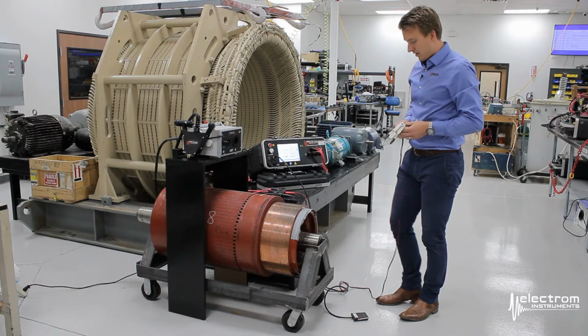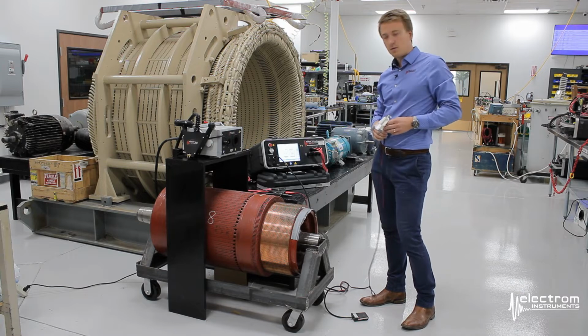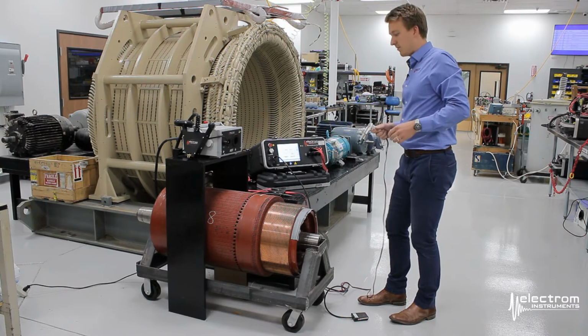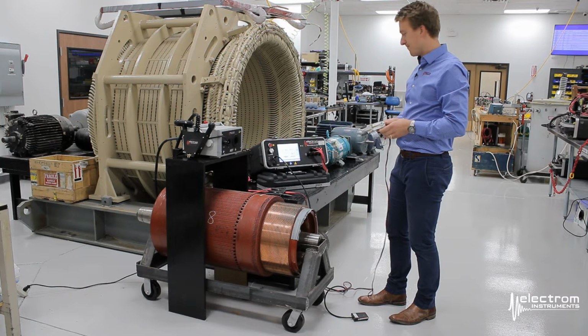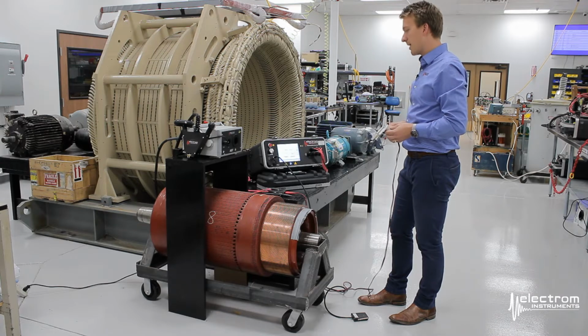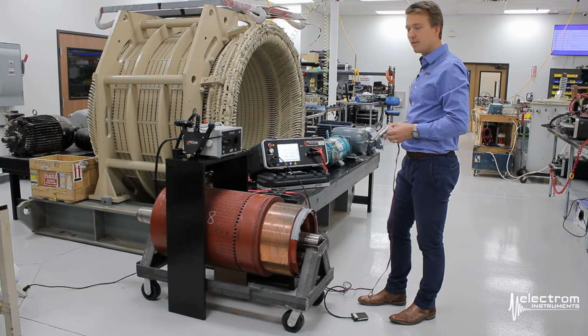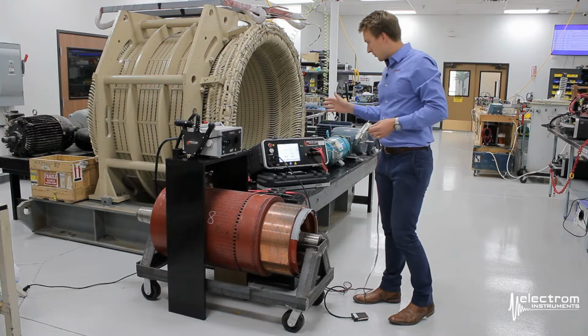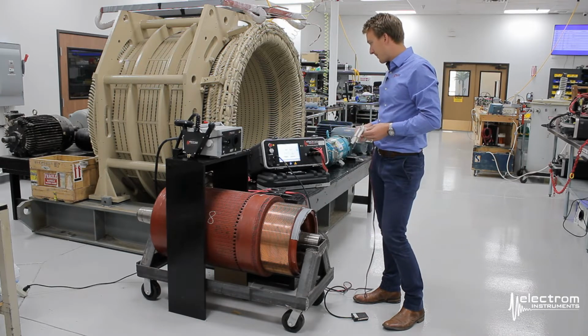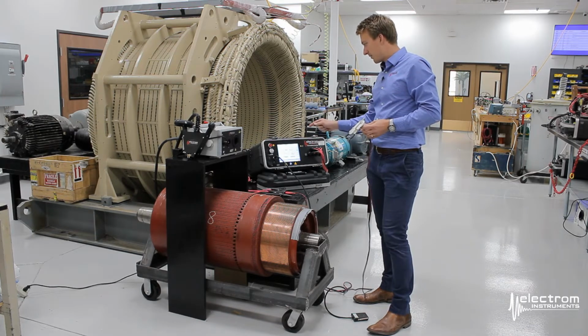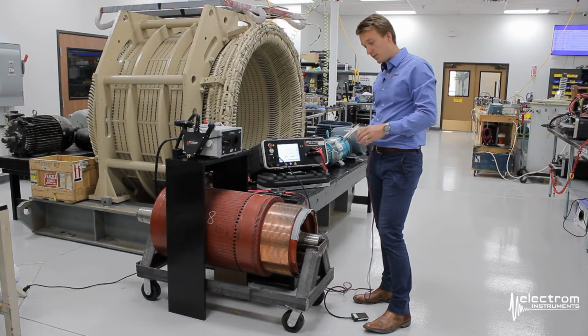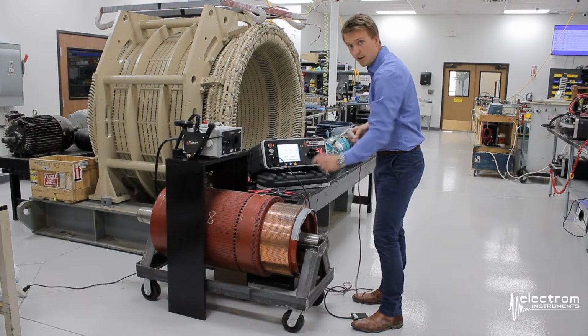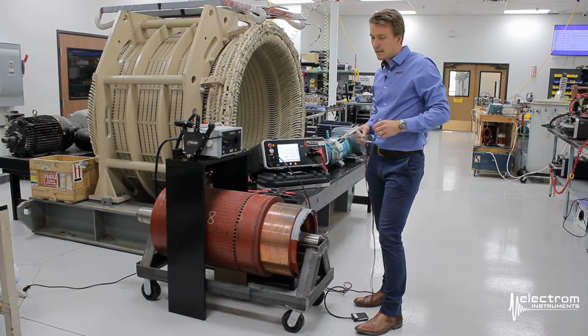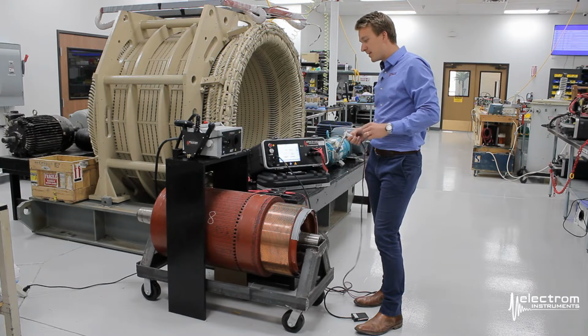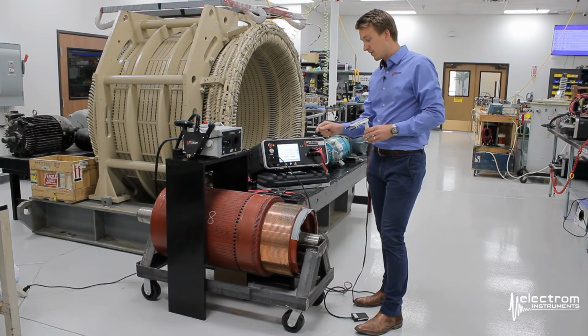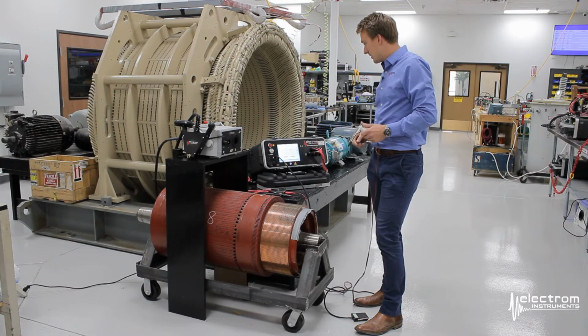For easy operation, it's recommended to use a foot switch. You can do this without one too, but it makes your life a lot easier if you have one. The test setup is similar to that of the ABT. So we're already in test mode here. I've set the surge test volts to 350. As mentioned, that means the voltage applied bar to bar is likely going to be a little bit lower. It depends on the inductance or impedance of the coil itself.